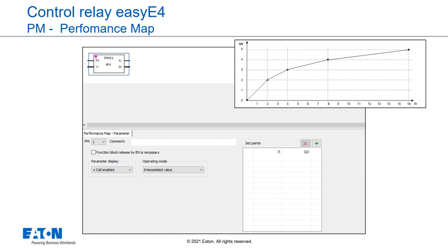The reference value table needs to be filled with at least two and at most 32 values for I1 and QV beforehand. If a value that is not found in the table is present at the function block input, the operating mode being used will determine which value fits the best and will be output at the function block output.